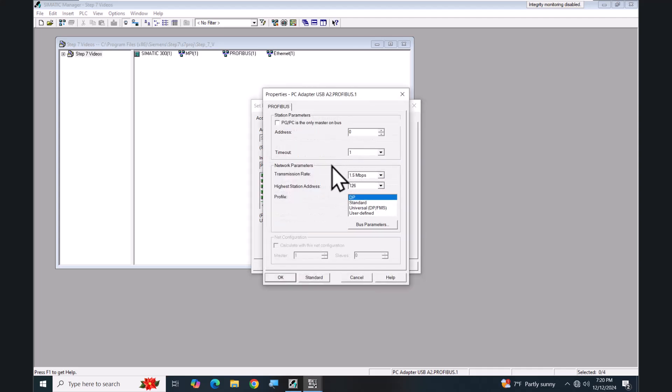This will show you the properties for the connection. The address zero is the address of the programming device. Then you've got your network transmission parameters as far as the baud rate on PROFIBUS goes, and then you want to make sure that your highest station number is at least as high as the highest PROFIBUS address on your network.